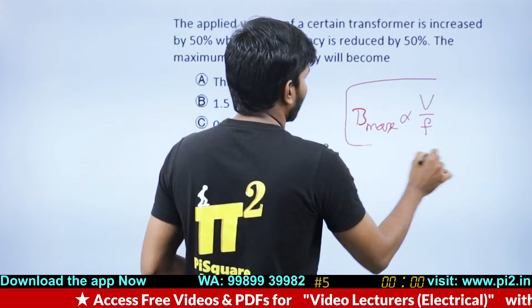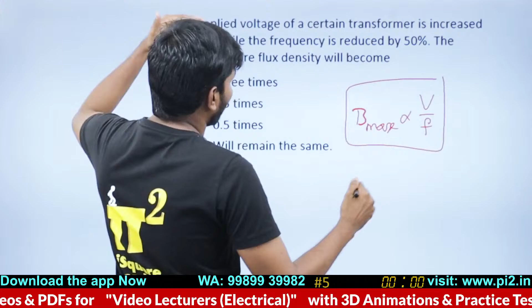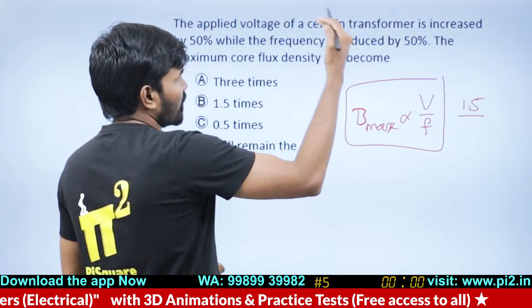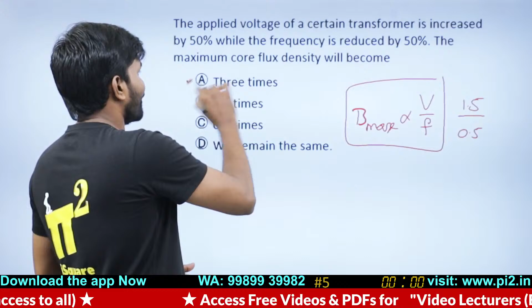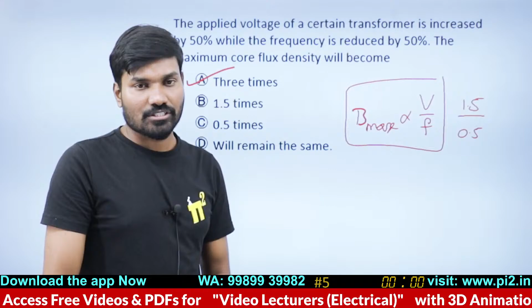Maximum flux density is proportional to V by F, voltage by frequency. Now voltage has increased by 50%, so take it as 1.5 times. Frequency has reduced by 50%, so it was earlier 1, now it is 0.5. The change in flux density is 3 times. Wow, Sai Ganesh has given that part also. Yes, it is 3 times, 1.5 by 0.5 is 3 times. Okay, Sai Ganesh, good one buddy, this is for you. Moving to the next question.